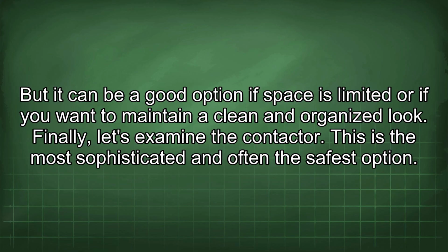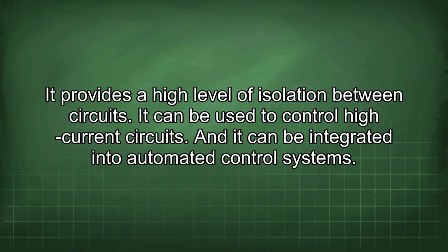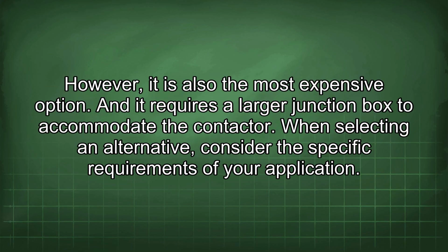Finally, let's examine the contactor. This is the most sophisticated and often the safest option. It provides a high level of isolation between circuits. It can be used to control high current circuits, and it can be integrated into automated control systems. However, it is also the most expensive option, and it requires a larger junction box to accommodate the contactor.